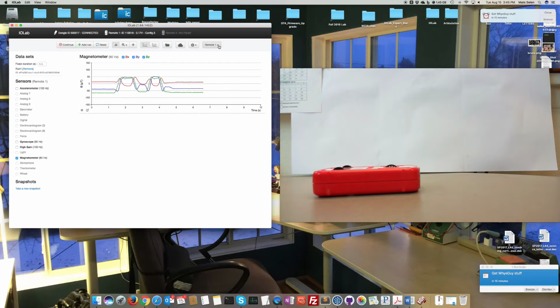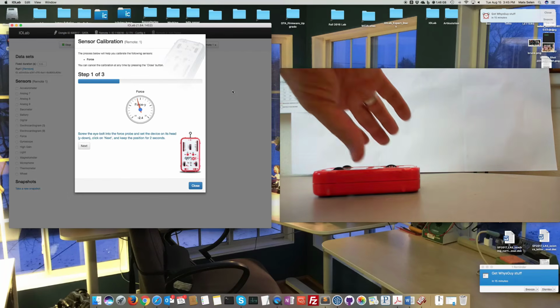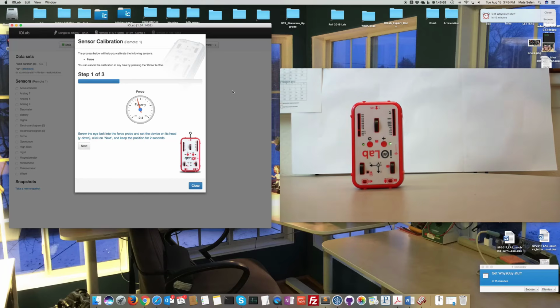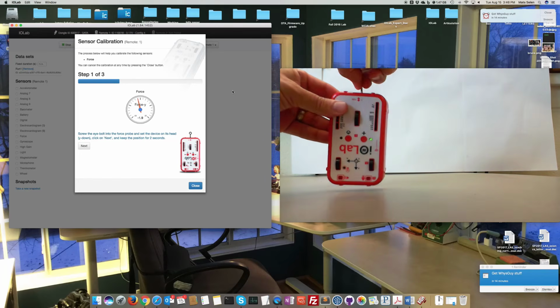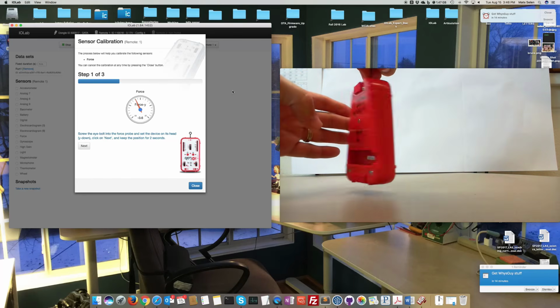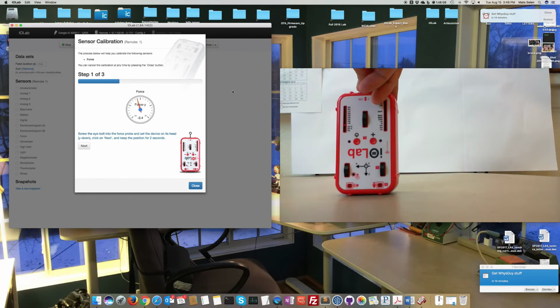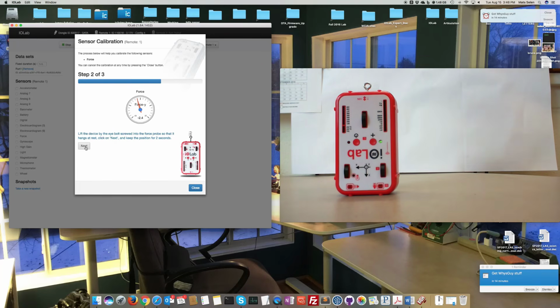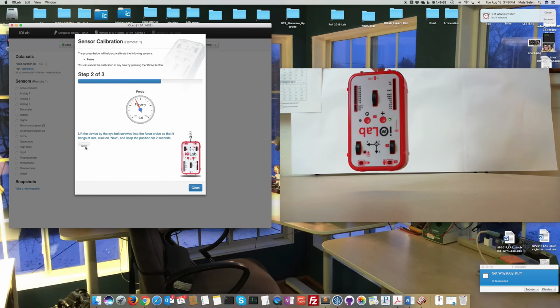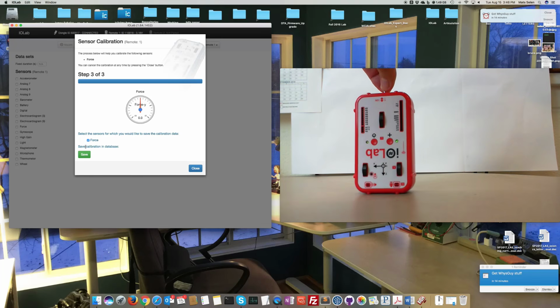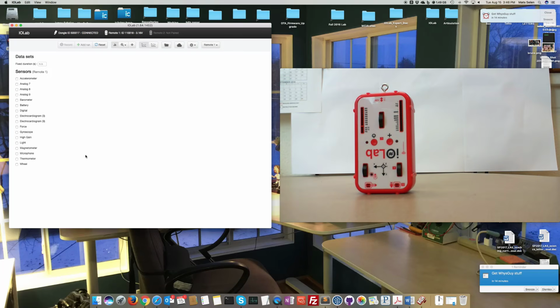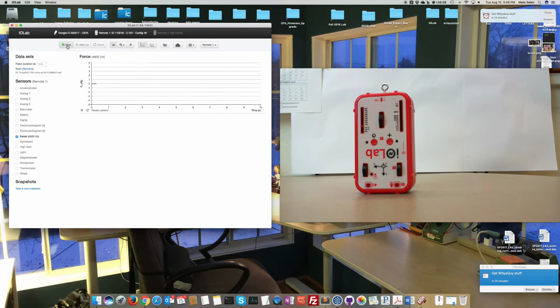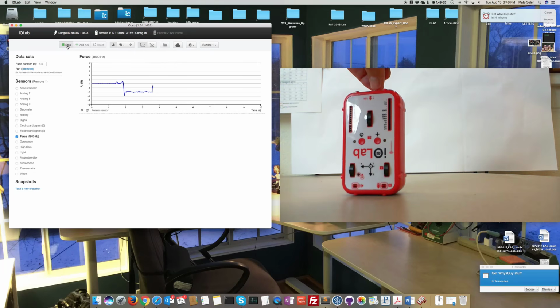Okay, so the next thing we're going to do is calibrate the force probe. So we select force over here, and it tells us to take the device, and we're going to screw in the little eye bolt that comes with it so that we can lift it, but we're not going to lift it yet. The first step is just to have it sitting on its own without any force being applied. Second step is to lift it up, hang it by its own weight, take data again, and so we use the weight of the device to calibrate it, and we save that data. Now when we accumulate force data, we see that this thing weighs 2 newtons.